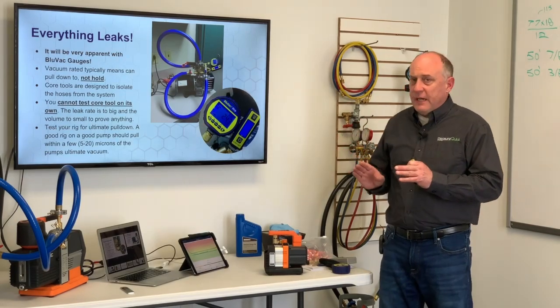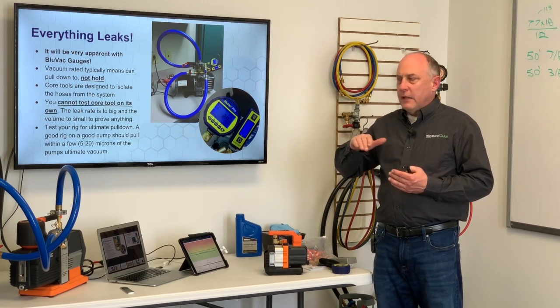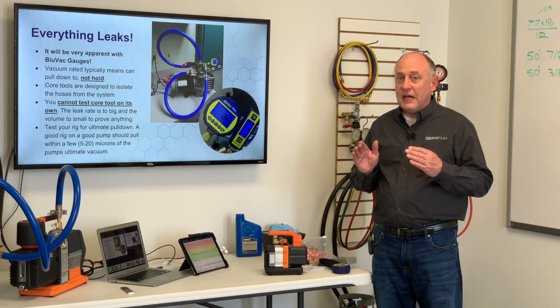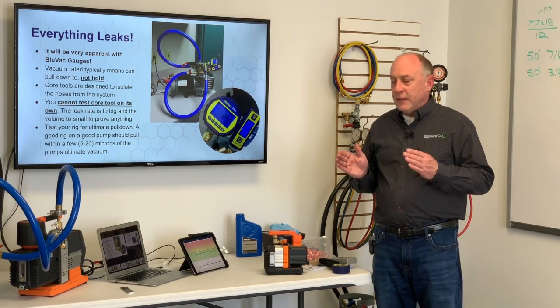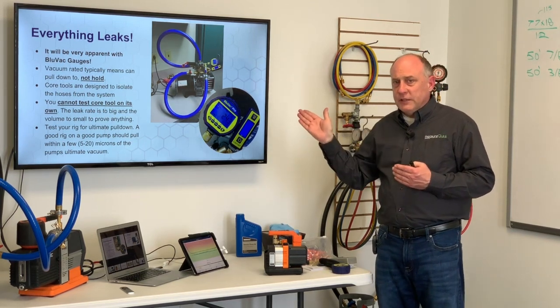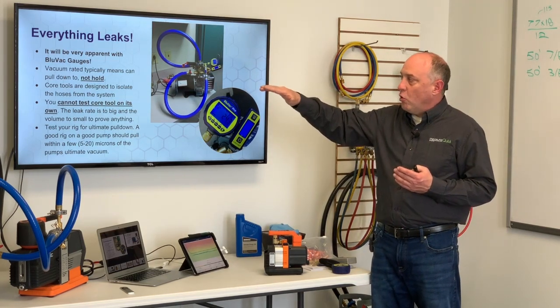Everything leaks, and this will be very apparent with your BluVac gauges. When you isolate the system, you're going to see that level of decay. You've got a vacuum gauge that has a resolution of 0.1 microns, and it's very seldom that that 0.1 micron indication is going to stop moving. What we want to make sure is that our vacuum rate of decay is less than 1 micron per minute. That's the beauty of the pro gauge — the computer can tell us when the rise rate is low enough. Our hoses have one of the lowest leak rates in the industry. Vacuum rated means it can pull down, not necessarily hold. It's the leak rate we're concerned with.